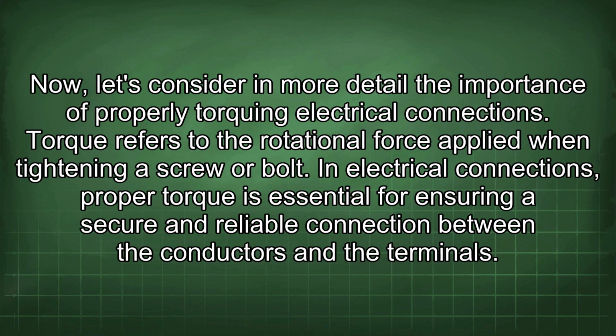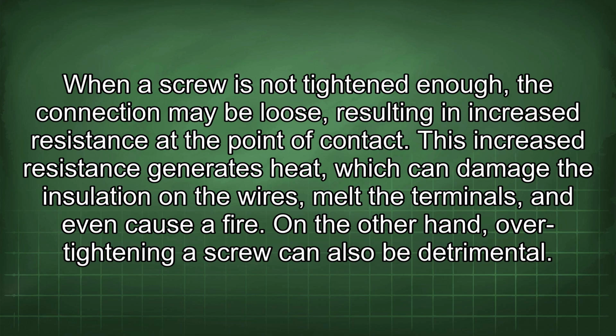Now let's consider in more detail the importance of properly torquing electrical connections. Torque refers to the rotational force applied when tightening a screw or bolt. In electrical connections, proper torque is essential for ensuring a secure and reliable connection between the conductors and the terminals. When a screw is not tightened enough, the connection may be loose, resulting in increased resistance at the point of contact.